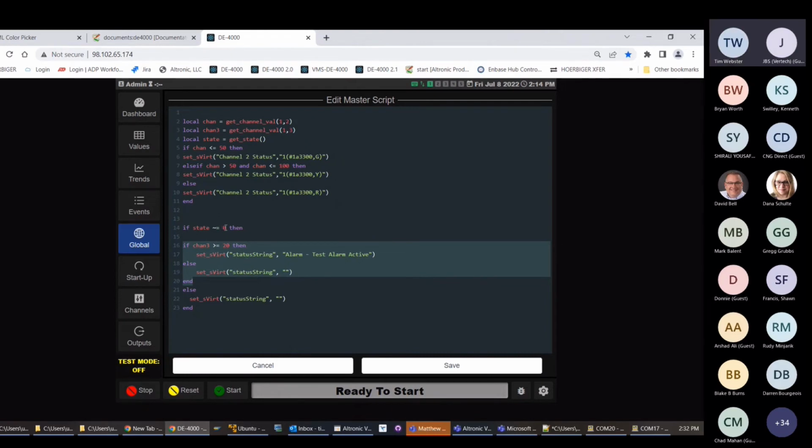And if we are in state zero, it's always going to default to status string blank, so that'll clear it. If you go into a fault, the system will go into state zero. It'll shut down and clear any alarms you had, and that will allow the shutdown fault message to be displayed. Good question though.